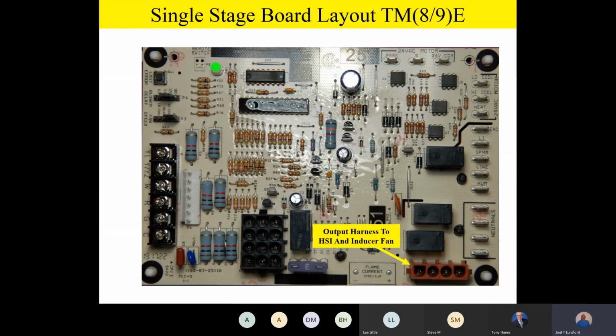Now, at this time, I'd like to go ahead and stress something to everyone. All the harnesses from the factory are hooked up to this board. In other words, these output harnesses to the hot surface igniter and the inducer fan are all hooked up at the factory. So when we're doing our training today, team, please bear in mind, we've removed all the harnesses just so we could talk about the board and the components on the board, and it makes it easier to look at the board if the harnesses are off. But as an installer, you don't have to hook all this up. I just wanted to remind everybody that we've taken the terminals off the board just so that we could talk about them in class. So that's where your output harness goes to your hot surface igniter and your inducer fan motor.